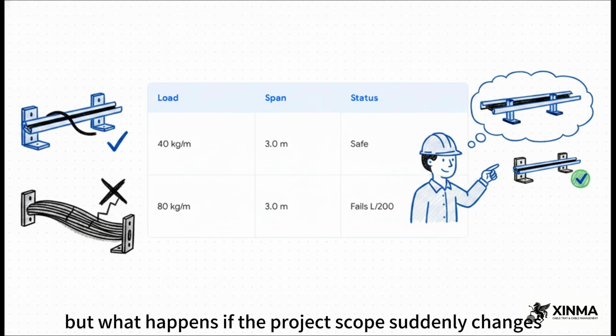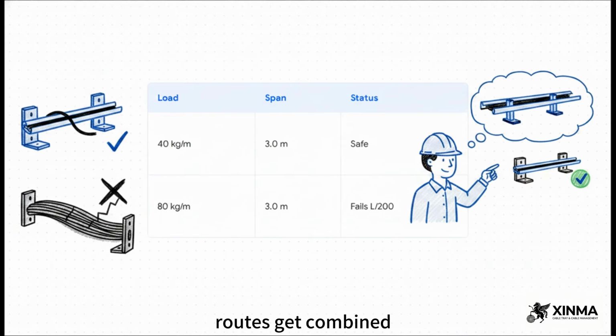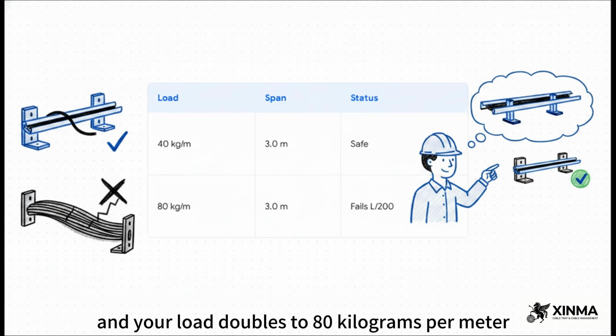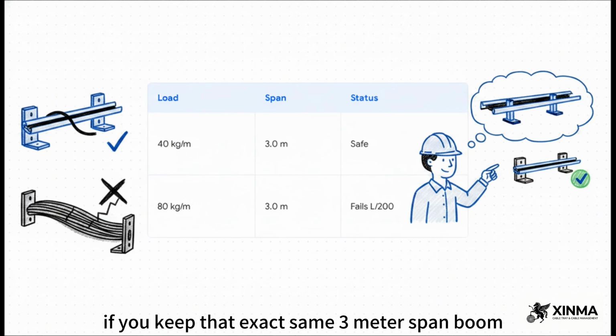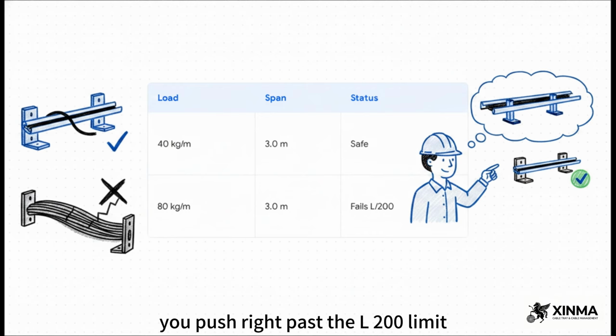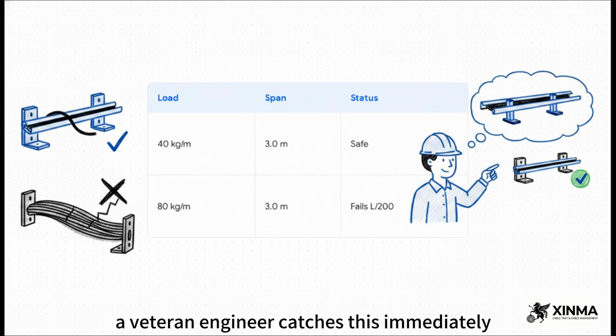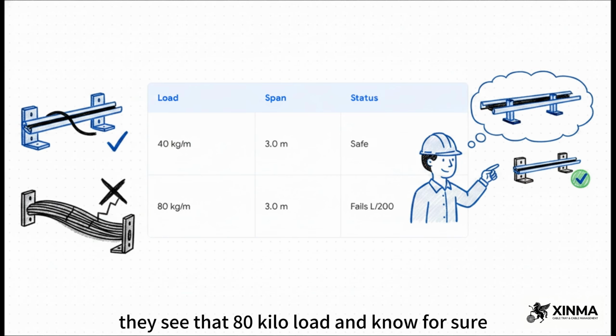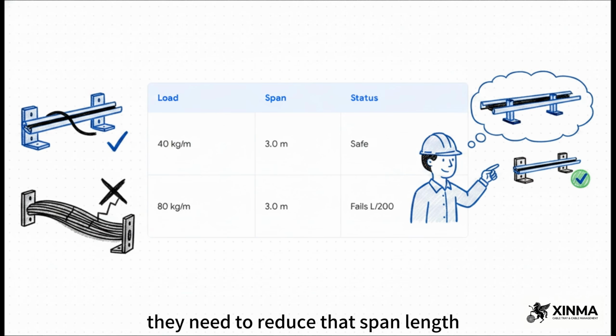But what happens if the project scope suddenly changes, routes get combined, and your load doubles to 80 kilograms per meter? If you keep that exact same 3-meter span, boom! You push right past the L/200 limit. The system fails. A veteran engineer catches this immediately. They see that 80-kilo load and know, for sure, they need to reduce that span length, maybe moving brackets every 1.5 or 2 meters.